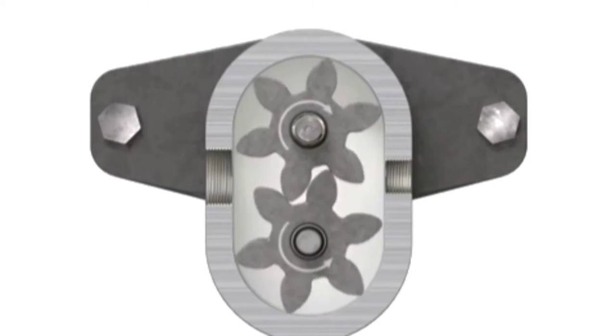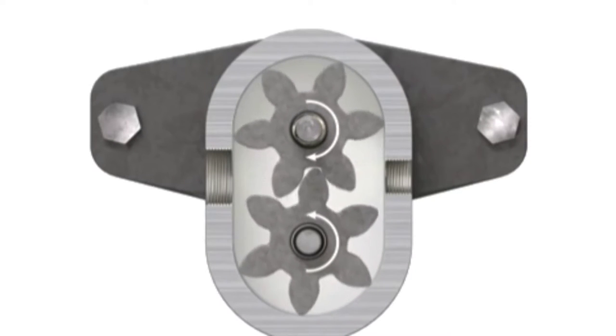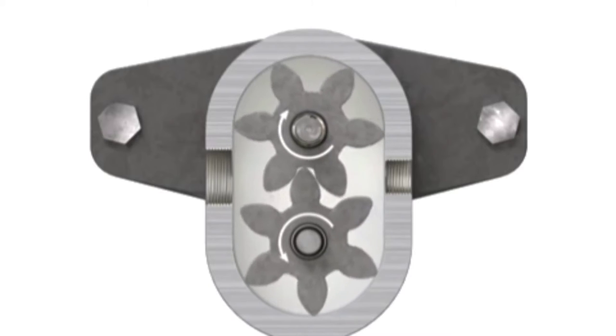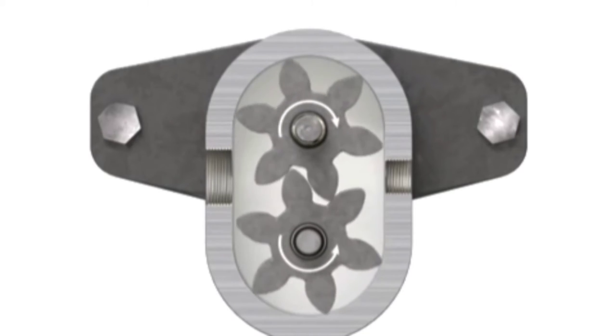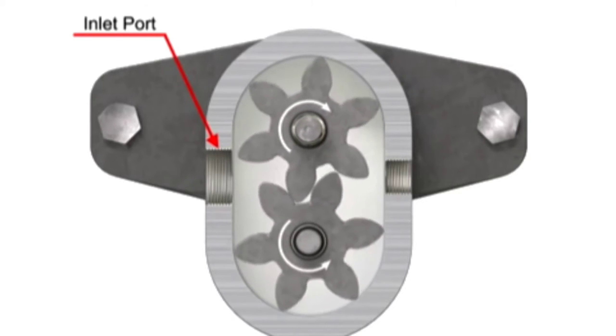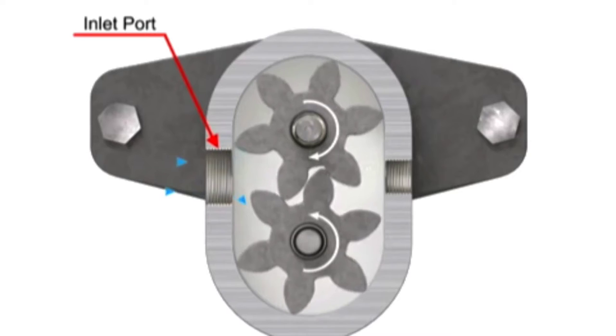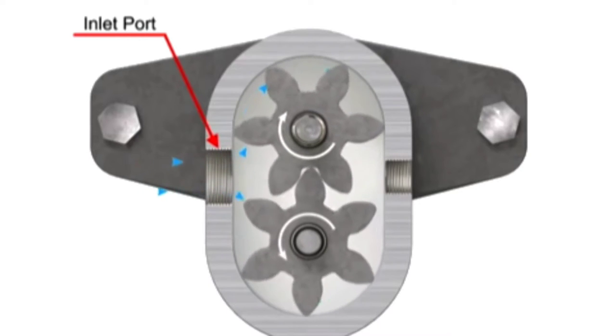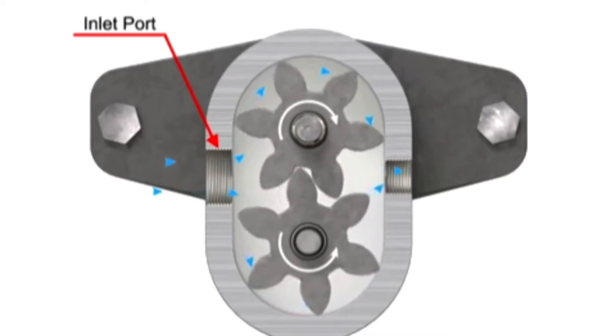As the gears rotate away from each other and come out of mesh, they create an expanding volume on the inlet side of the pump. This creates a vacuum at the inlet port allowing fluid to flow into the pump. Then fluid flows into the cavities and is trapped by the gear teeth.